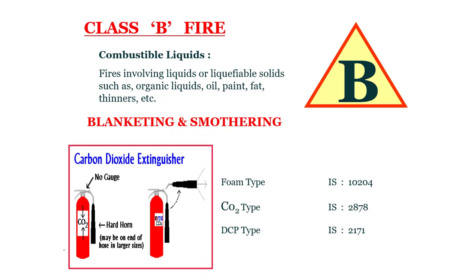Class B fire — combustible liquids: fire involving liquids or liquefiable solids such as organic liquids, oil, paints, fat, thinner, etc. To extinguish this Class B fire, blanketing and smothering is recommended — mainly by disconnecting the oxygen. Carbon dioxide extinguishers are used. Foam type IS 10204, CO2 type IS 2878, and DCP type IS 2171 are recommended for extinguishing Class B fire.